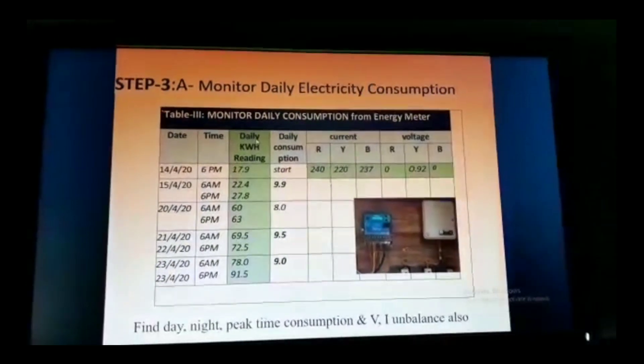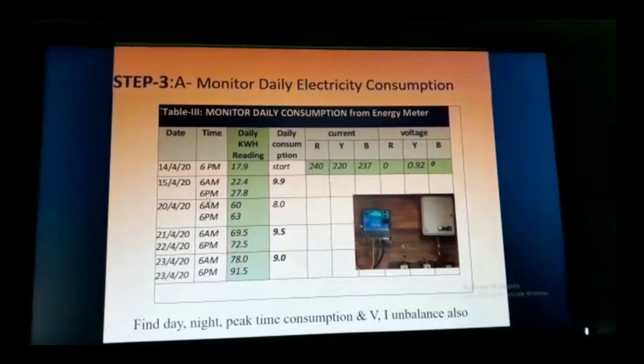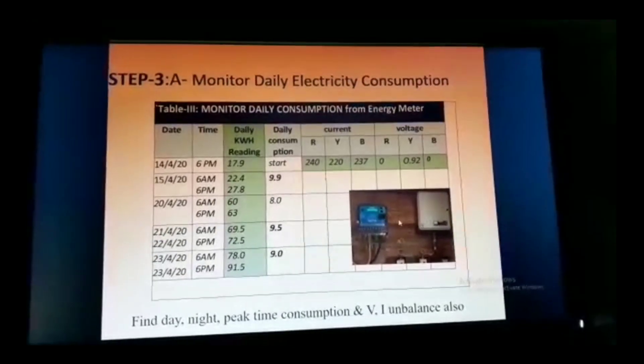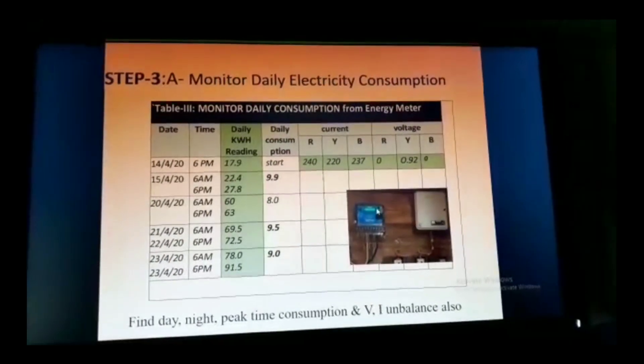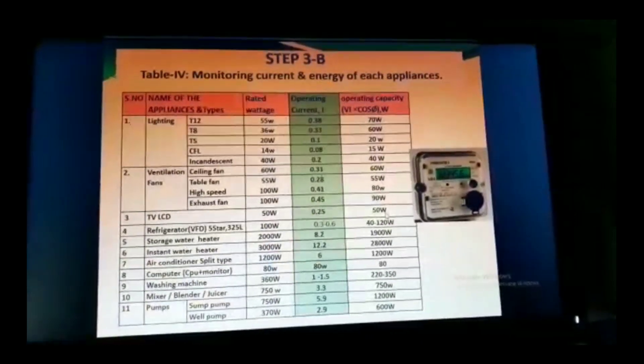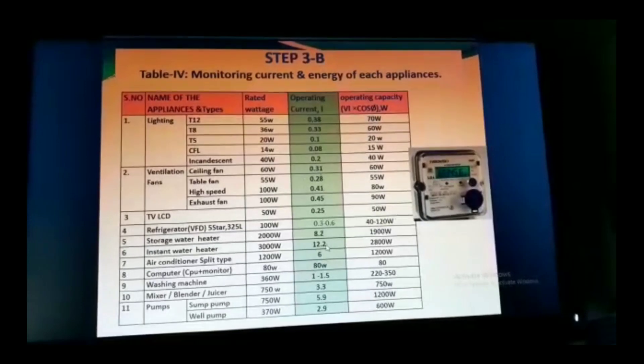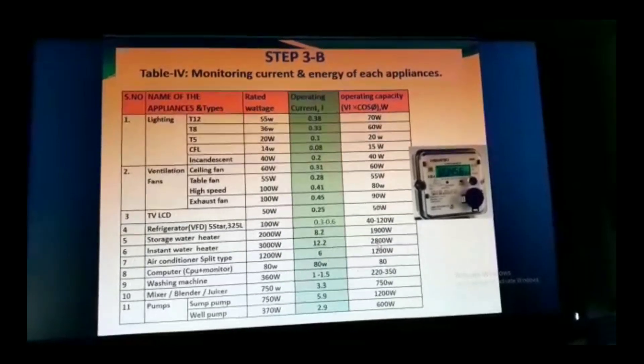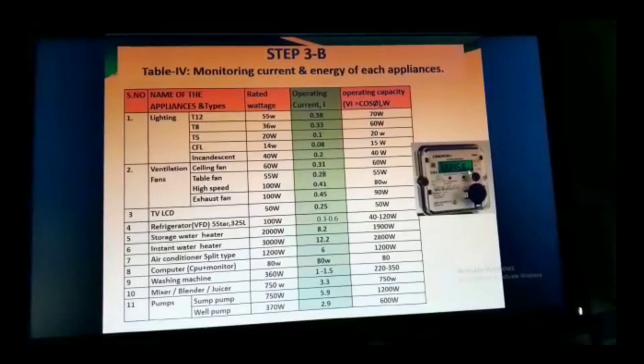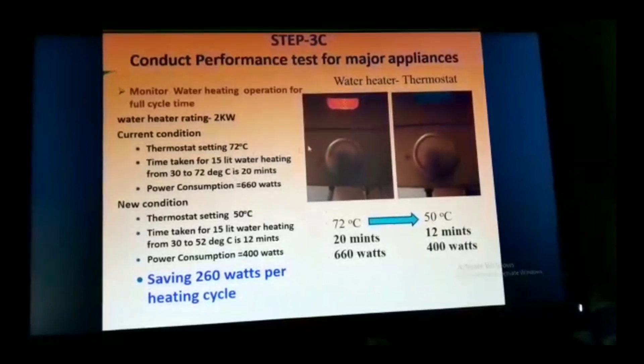Now move on to energy monitoring. If you are not monitoring, you cannot manage — that is the principle. In the home, note down every day morning and evening how much is consumed. You will find daytime, nighttime, and peak-time consumption. The energy meter is very important: it shows voltage, current, three-phase supply balance, and imbalance. To find the exact capacity of equipment, record the amperage. For example, an instant water heater takes 12.2 amps and consumes 2.8 kW. Running individual appliances and noting these readings is very useful for calculations.